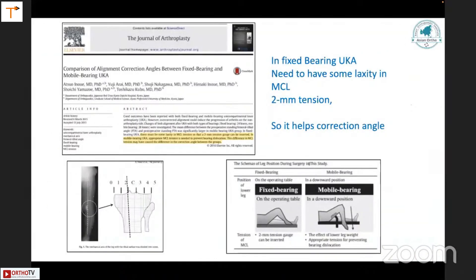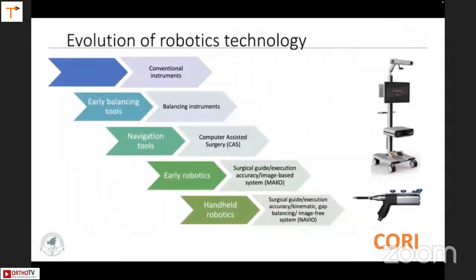The difference between mobile and fixed bearing: in a fixed bearing we need two millimeters of laxity across the joint. How do you confirm that two millimeters of laxity? We need some tool to tell us the two millimeters is achieved. This drove the evolution of technologies from conventional balancing instruments to CAS to handheld robots and now full robots.